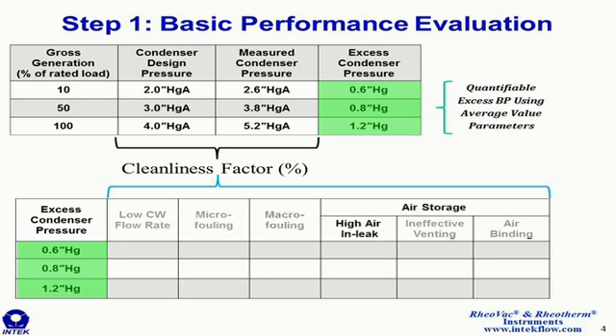But then there's a whole other class of degradation mechanisms called air storage. Air storage is pockets of high partial pressure of air that greatly reduce heat transfer around tubes that are airbound. Everybody's familiar with problems of high air in-leakage and how it can cause high condenser pressure. But similarly, low venting equipment capacity can also cause air storage. Examples of this are if the venting equipment is, say, liquid ring vacuum pumps, then a damaged impeller or high seal water temperatures will decrease the venting flow rate and result in air storage. If the venting equipment is steam jets, then low motive steam pressure or high intercondenser pressures are causes for low venting capacity. Even the vacuum equipment layout can cause air storage.